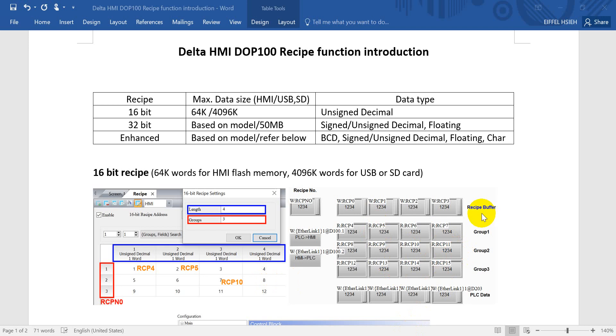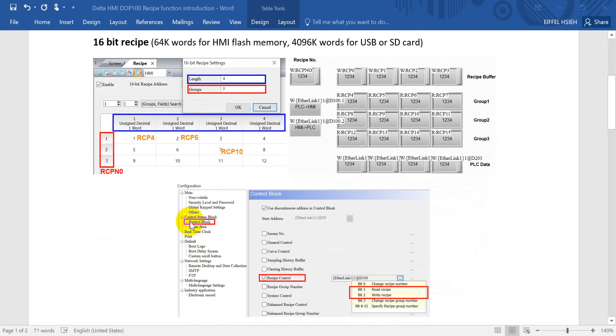For recipe applications, some customers prefer to save the recipe from inside the HMI and then write to the PLC. But some customers prefer to get the recipe from the PLC and update it to the HMI. To achieve that, we can use the control block. You can see the recipe control. For recipe control bit 1, that means read from PLC to HMI. And write recipe means it will write the HMI recipe to the PLC.